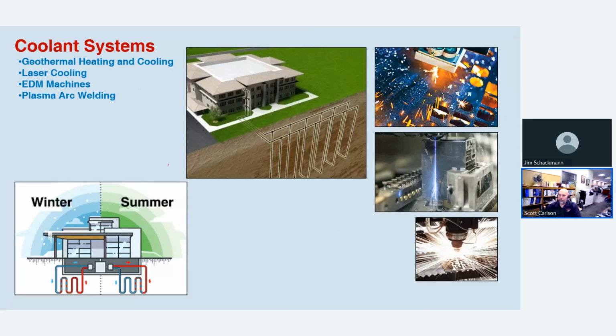Next on our list here is cooling systems. Any kind of circulation for fluids, whether it be geothermal heating and cooling or any kind of equipment cooling, regenerative turbines are ideal for that. With the geothermal heating and cooling, when you have piping that goes down thousands of feet and then back up, there's a lot of twists and turns in the piping and a lot of elbows that cause a lot of friction losses. So to maintain that flow, you need a high pressure pump to overcome all those friction losses. So regen turbines are ideal for that.